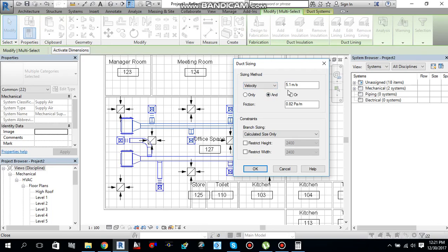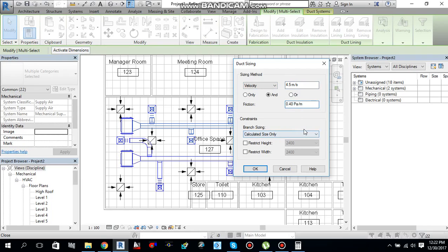As a general rule for fan coil units, 4.5 meters per second is the maximum velocity we will not exceed in the ducts. So I will select 4.5 meters per second. The maximum friction allowed for fan coil units is 0.40 Pascal per meter, so I will set that as well. Change the design velocity to 4.5 and friction to 0.40 Pascal per meter, then select OK.